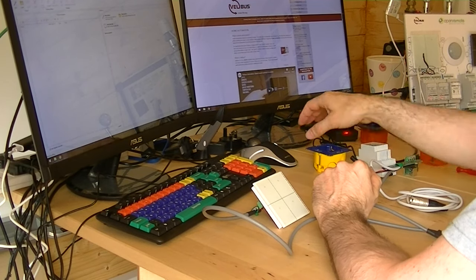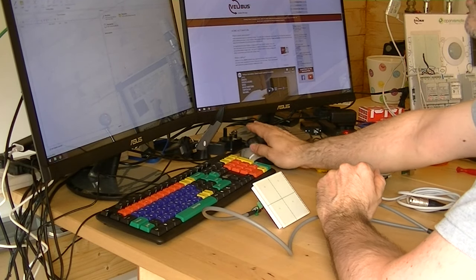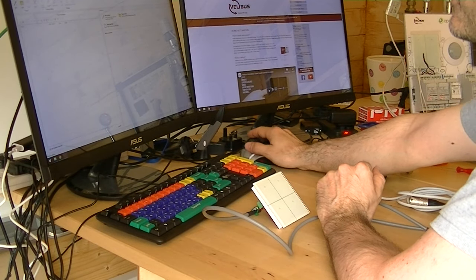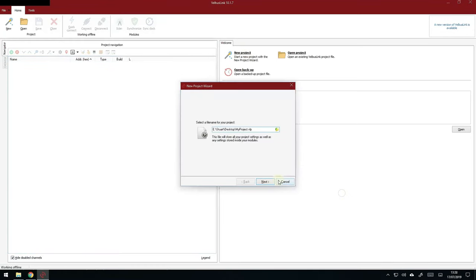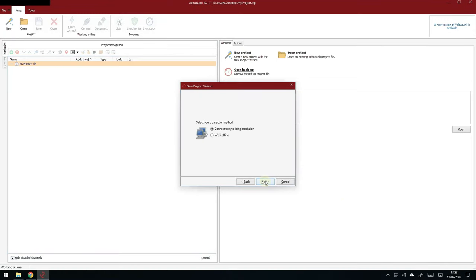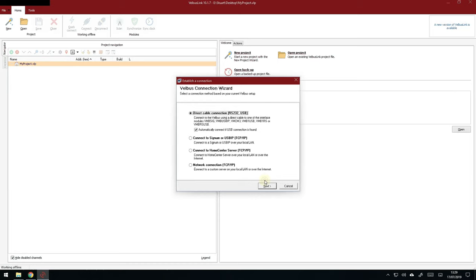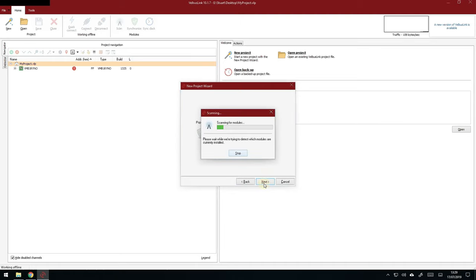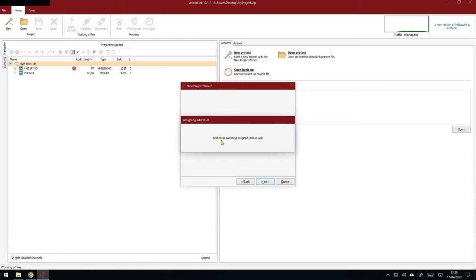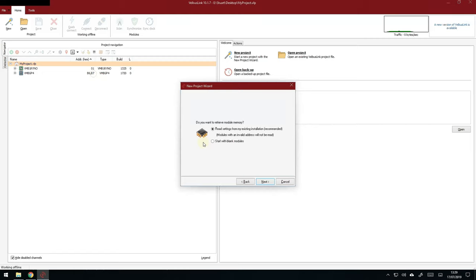So, on to the software. We've connected the USB and we've loaded Velbus Link. We've clicked on New Project. We've set a location and we're going to choose the USB connection that comes up by default. Click on Next. And we're going to scan for new modules. And I don't normally, but on this occasion, we'll assign addresses automatically because it really doesn't matter. So it's going to scan through and it's going to find the two modules that we've connected up already. There you go. And I'll just let it zip through to the end there. There we go. Now it's just double checking the addresses are correct. It's going to assign something. You'll see the FF change to 01. There it goes. So, essentially that's all configured.